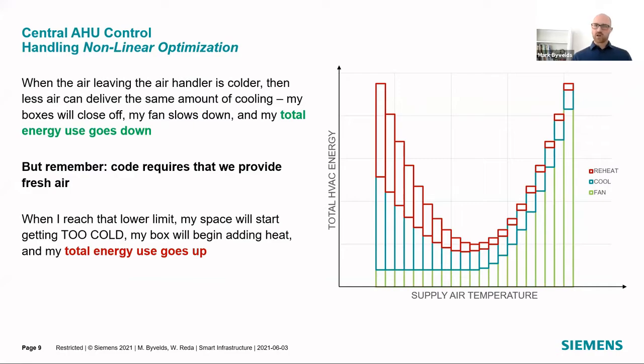To make the graph a little more colorful and put it into perspective, with these VAV systems, think about where the energy inputs are: a fan pushing air through the system, energy to cool the air, and in many cases energy to heat the air as well, the reheat. To keep a space happy in a variable air volume system, we need to put fresh air through it, and we need it to be conditioned. What we see on this graph are different points along a spectrum that achieve the same end goal, but at different levels of energy consumption.